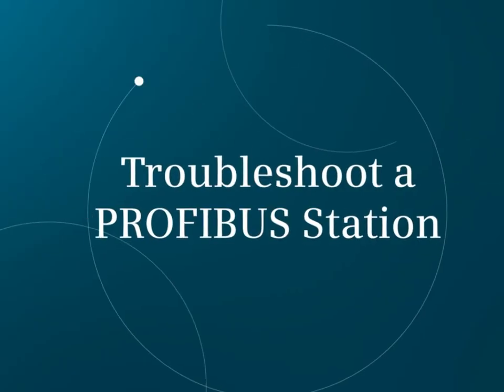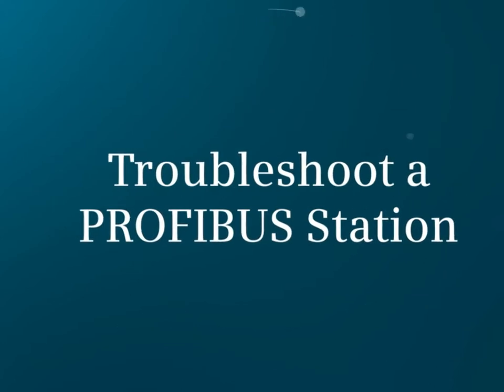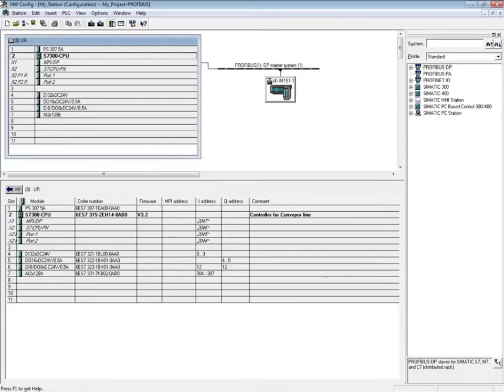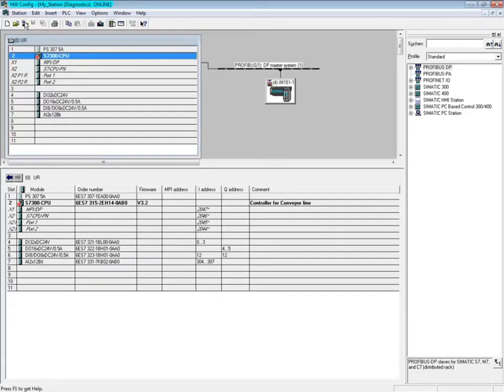In this video, you will see how to troubleshoot a PROFIBUS station that is down. In the Hardware Configuration Editor, click the Online button. Placing the hardware configuration online shows a graphical representation of where problems exist. In the Online view, double-click the CPU to open the Module Information tool.